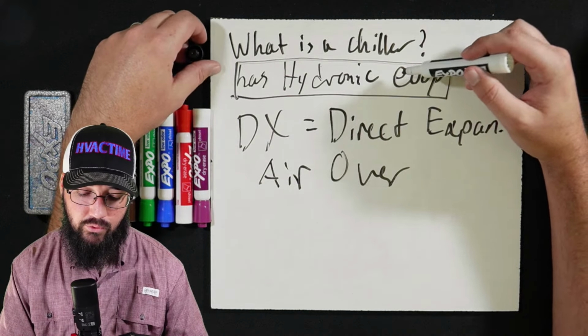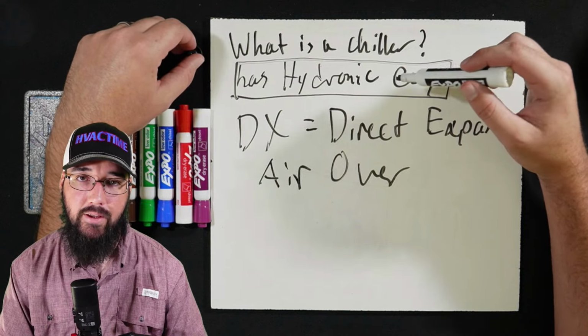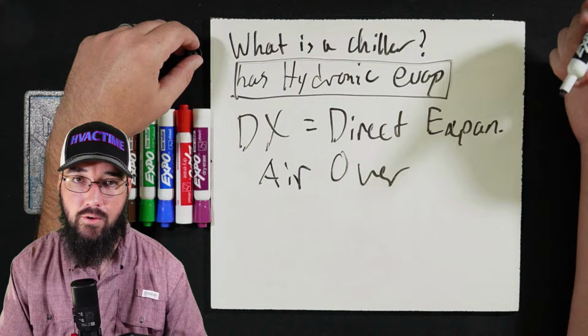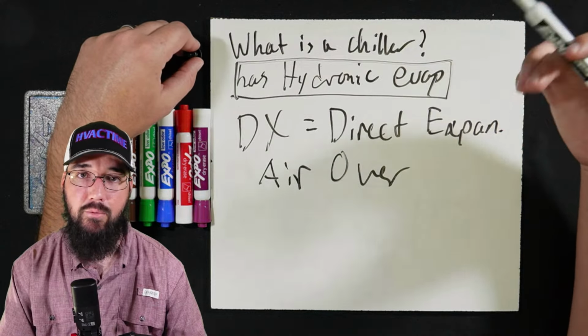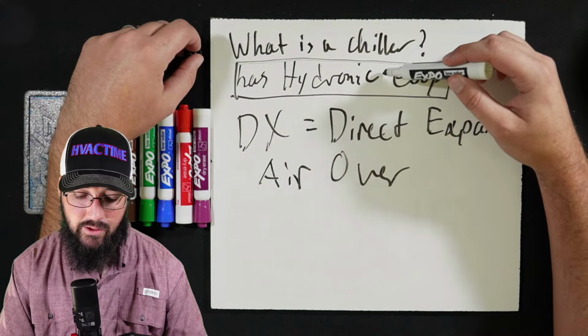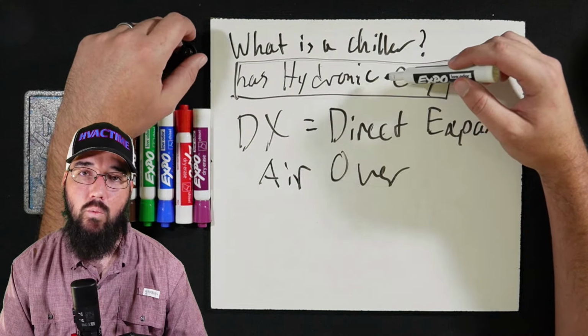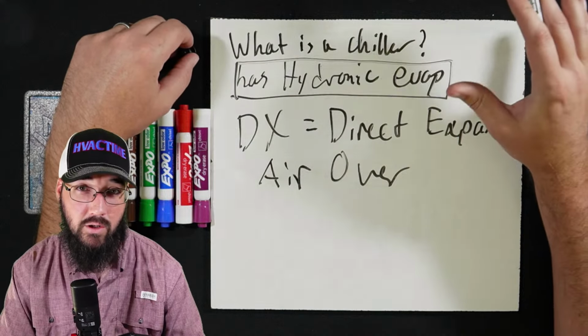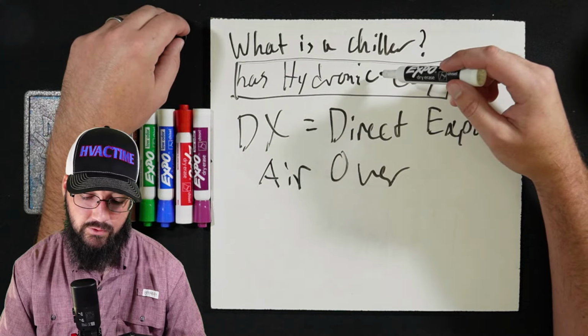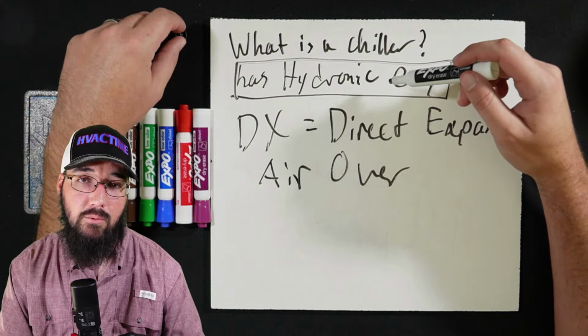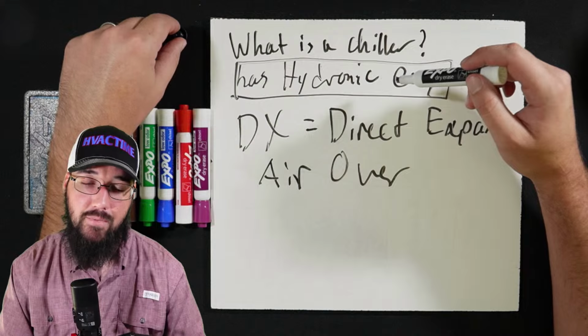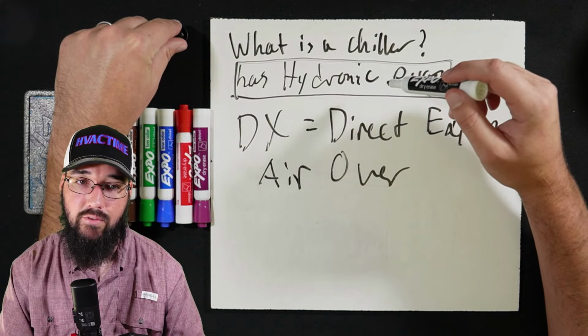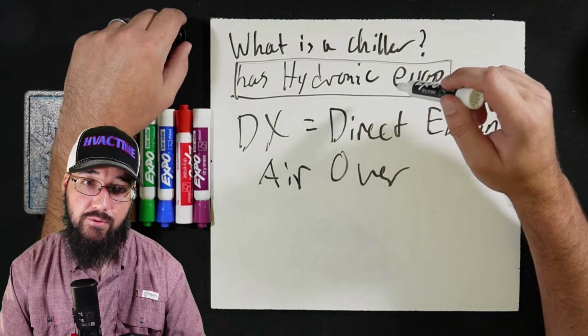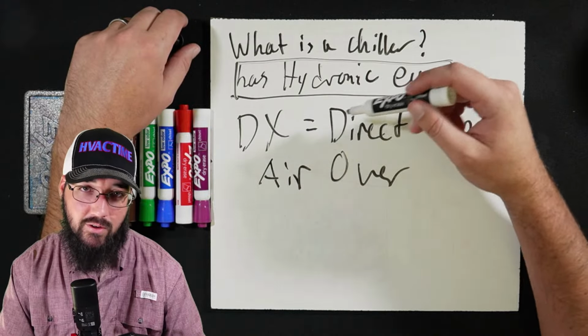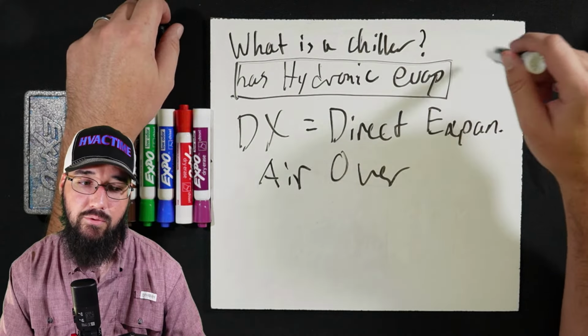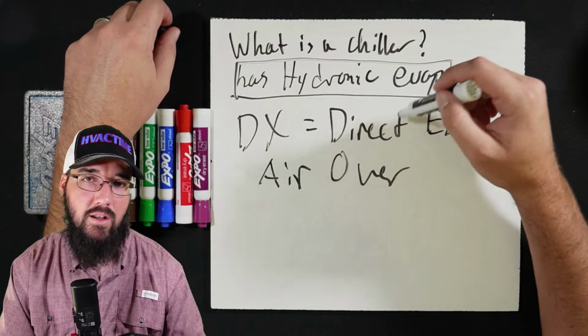A chiller, we don't have our refrigerant having a direct expansion process on the load itself in the airstream or in the coil or anything like that. Instead, our evaporator is processing water or some fluid. Maybe it's not even water. There are some cases in processing facilities we're not processing necessarily water, but we are processing a fluid. And that fluid is going through a hydronic evaporator. So the refrigerant stays localized to the machine, but so does an RTU, right? Now, a split system, sure, we send that refrigerant out elsewhere. So there's a lot of similarities here.